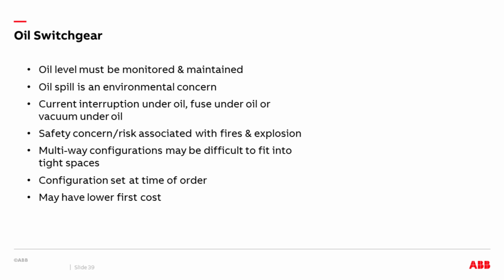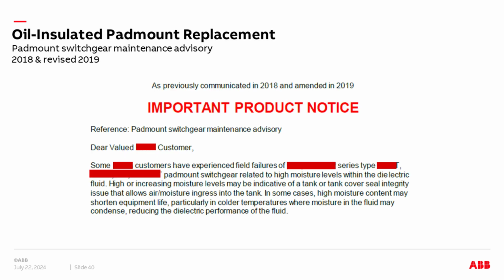So now I want to talk about oil to solid-dielectric conversions. Oil switchgear requires monitoring and maintaining. Oil spill is an environmental concern. The interruption is under oil normally, so there are some risks. Again, oil insulated gear has been around a long time with a very successful history, but all things that are aged can get to end of life and need an excessive amount of maintenance. So that could drive utilities to replace on different schedules, depending on what their asset management schemes look like.